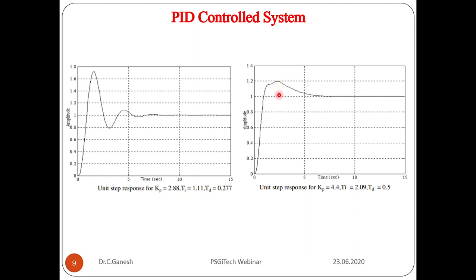Around 70% overshoot. So the system is highly oscillatory. Therefore, in real time, if you operate, it may even be unstable, that means continuously oscillatory. So after doing Ziegler-Nichols, I am doing fine tuning. By doing some fine tuning, I get the response like this. Here I can find that the overshoot is close to 20%.